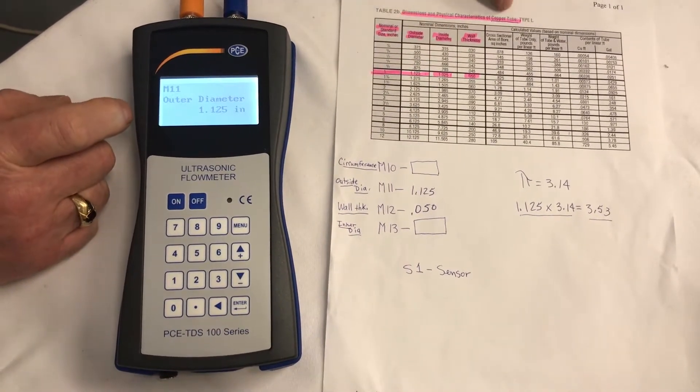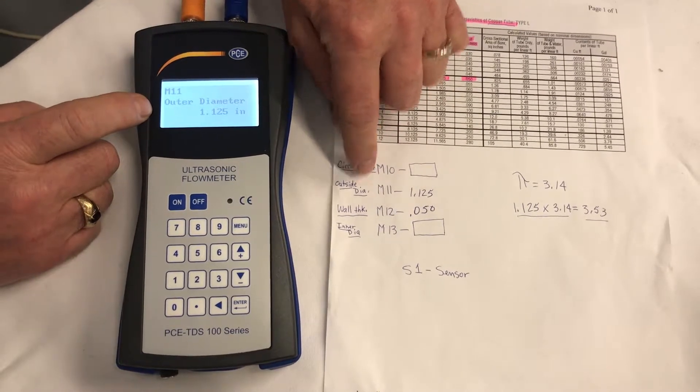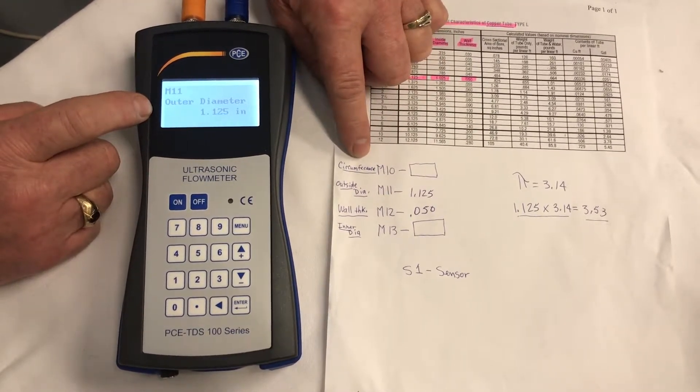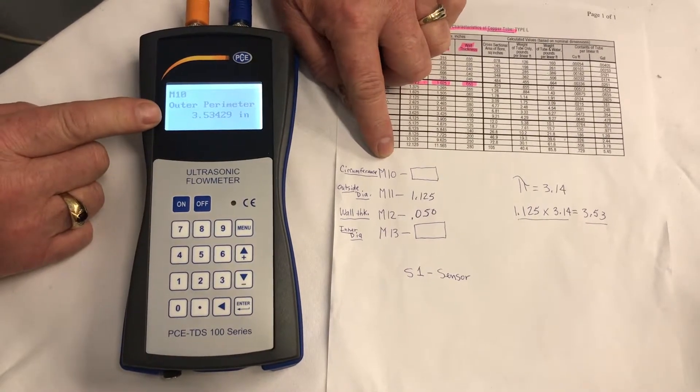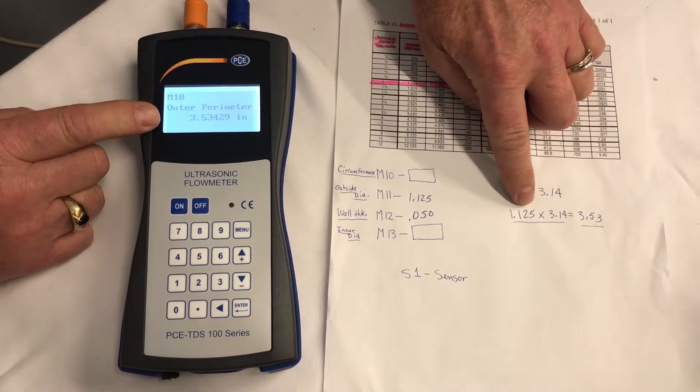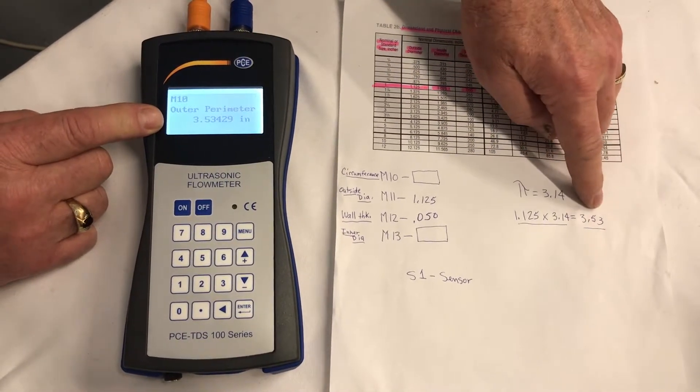Same as our chart for copper tube. If we put the outside diameter in, it figures the circumference for us, which is M10. So we go back to M10, and there it is, 3.53. 1.125 times 3.14, which is pi, equals 3.53. That's what the meter told us.